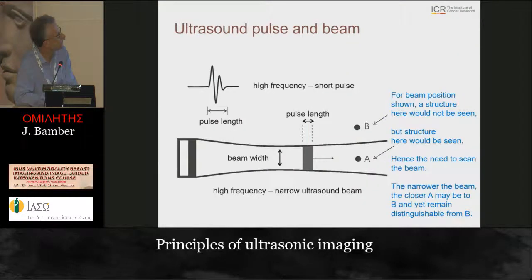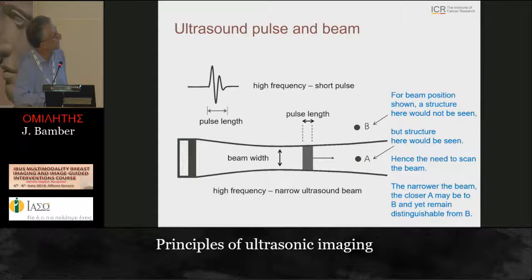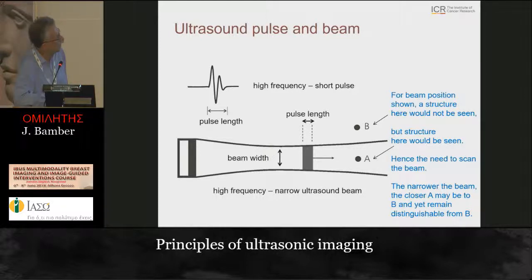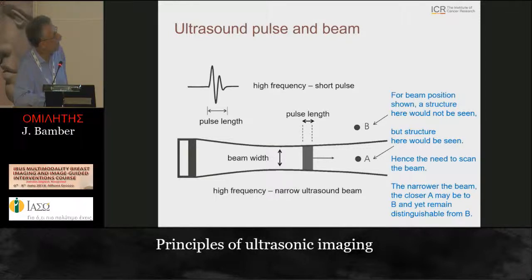Each tiny element can generate its own little sound wave, and that allows computer control of each element to focus the sound beam. Short pulses and narrow sound beams are generated this way. If a target is scattering sound back to the transducer, the sound beam is directed toward it; if another scattering object is elsewhere, it won't send sound back in that position, and you'd need to move the sound beam to see it - that's why we do scanning.